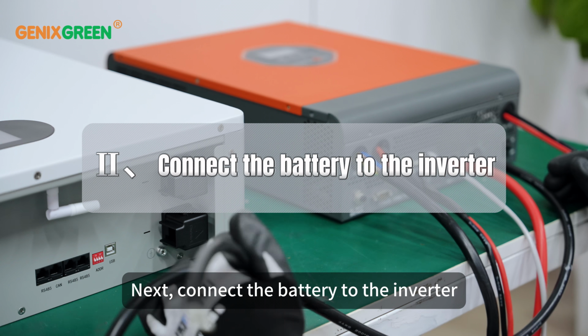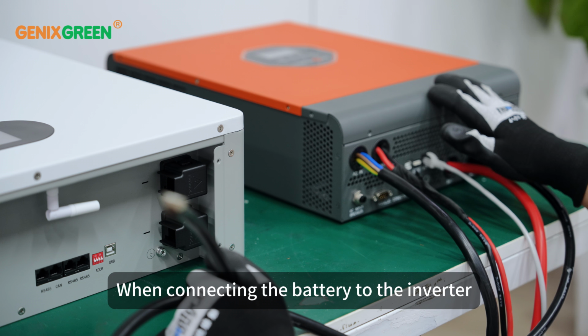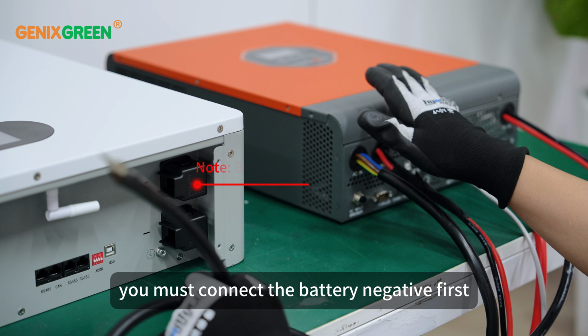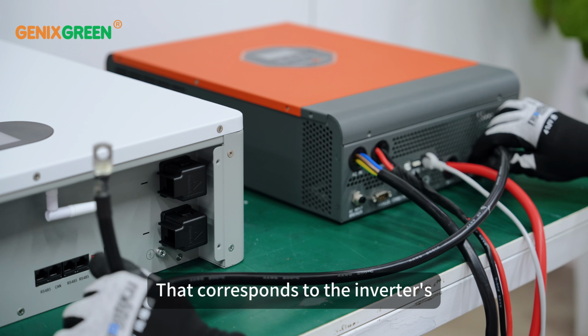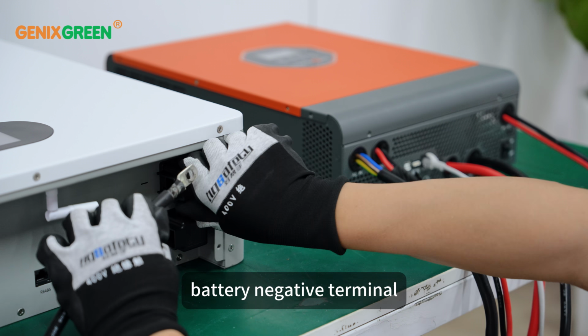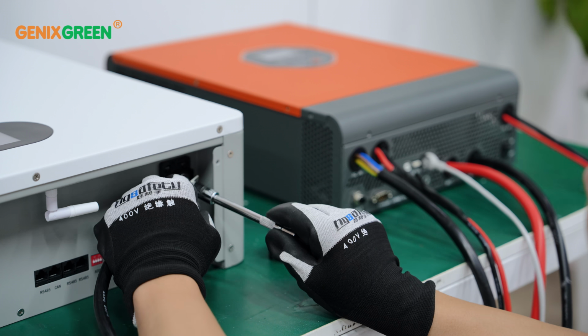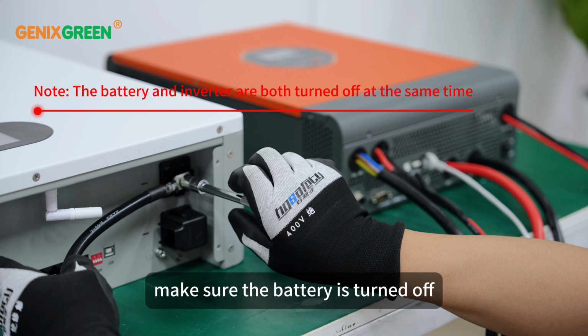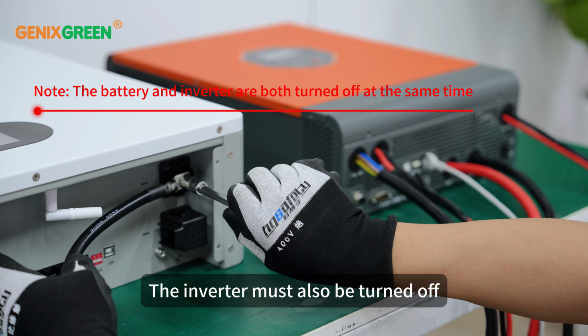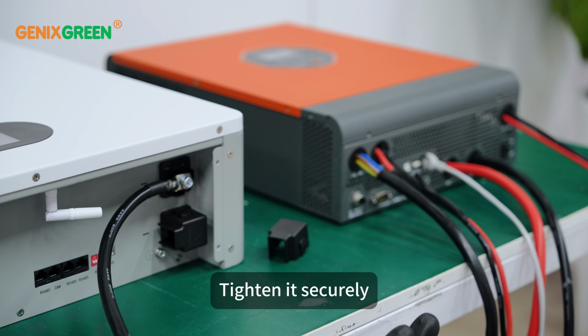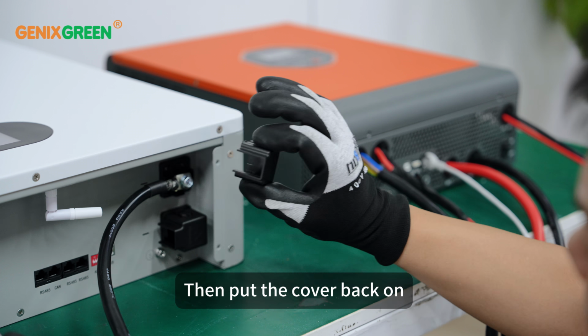Next, connect the battery to the inverter. When connecting the battery to the inverter, you must connect the battery negative first. That corresponds to the inverter's battery negative terminal. When performing this step, make sure the battery is turned off. The inverter must also be turned off. Tighten it securely, then put the cover back on.